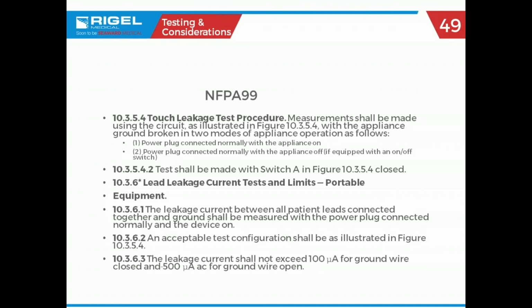We talked about testing leads, patient leads in 60601, where each lead is tested to ground individually, and each lead is tested lead to lead. NFPA 99 now says all of those patient leads, tie them together as a single point and test it that way. Normal operating condition, 100 microamps. Single fault condition, open ground, 500 microamps.